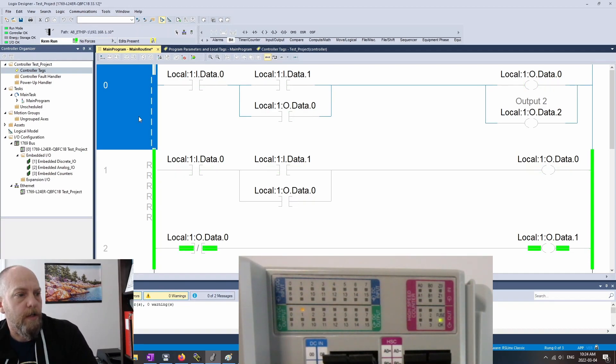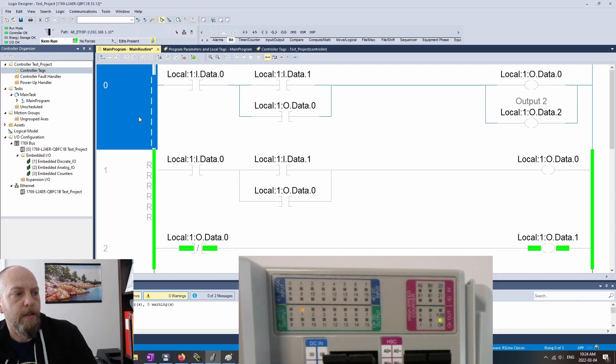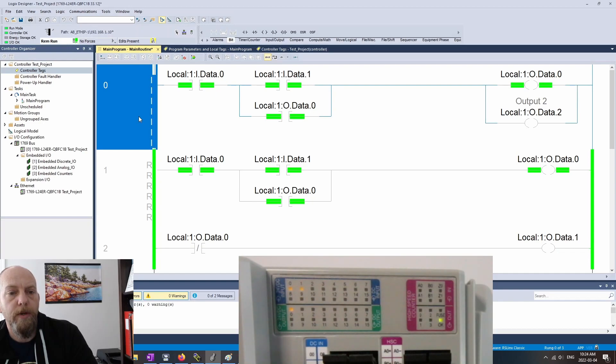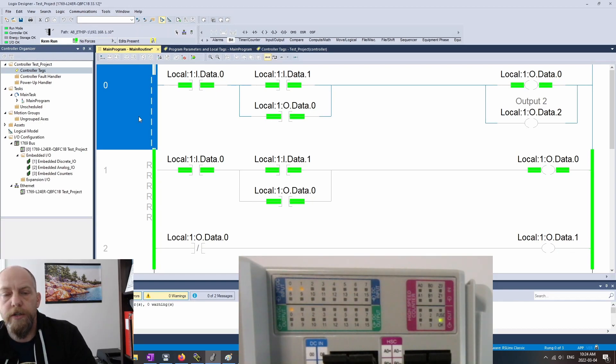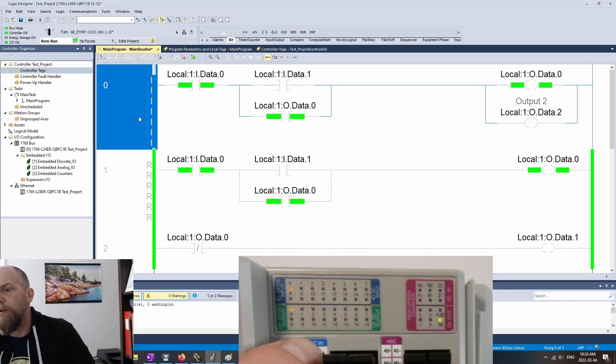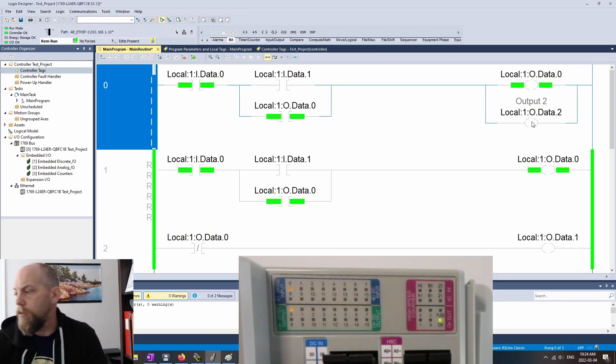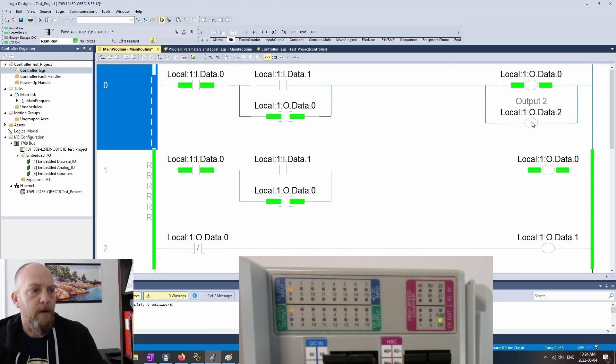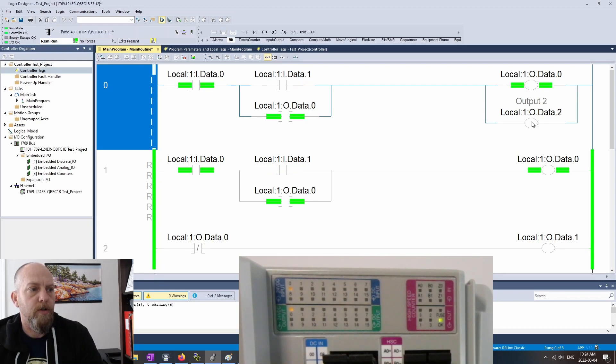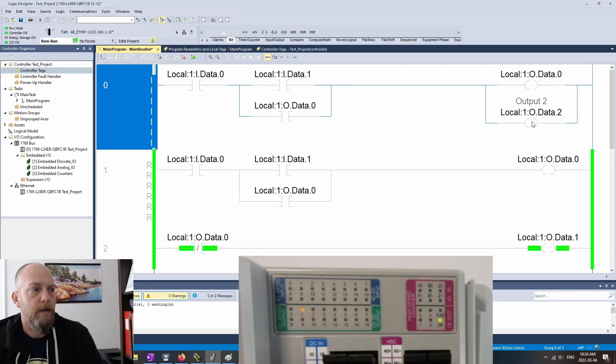If I did that a little bit too fast, if I hit the start push button, it looks like output 0 is turning on, but we can clearly see that output 2 is not turning on. We can see that here, and we can see that here as well. So I'm hitting the start push button, and one output is turning on, output 0, but output 2 is not changing state there.